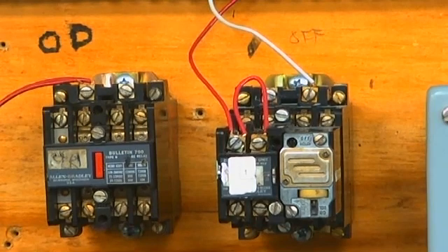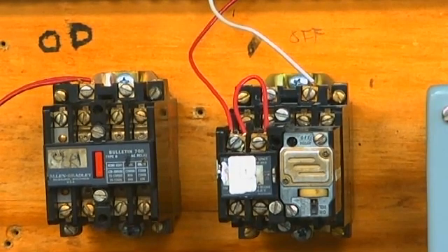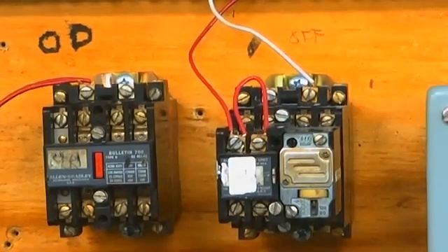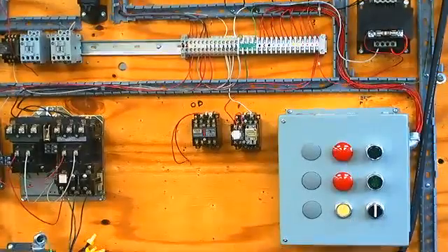When the coil gets de-energized, then 3 seconds later, it will change back, right? Does that make sense? You'll see it because I'm going to do an example. But an off delay timer means that when that coil gets energized, the lights are going to switch. And then after I de-energize the coil, 3 seconds later, it will change. Follow? So there's no timer when you turn it on. There's a delay in the off.